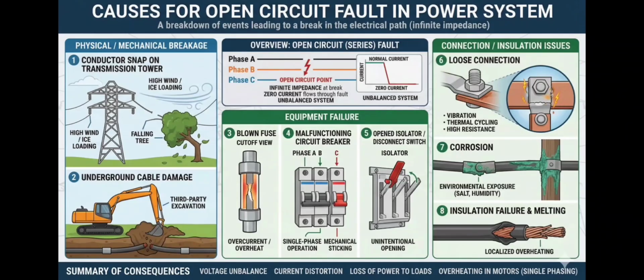And the malfunctioning of a circuit breaker. Usually, whenever any short circuit fault happens, the circuit breaker opens the contacts, and after the removal of the fault, it should close the contacts. But whenever, due to mechanical sticking, it fails to close the circuit, then we call it a malfunctioning of the circuit breaker, and this will lead to an open circuit fault.